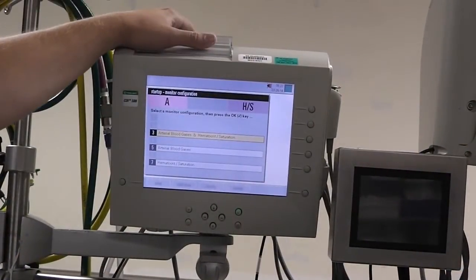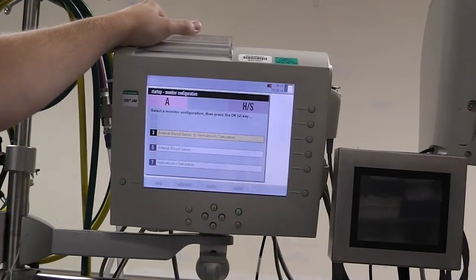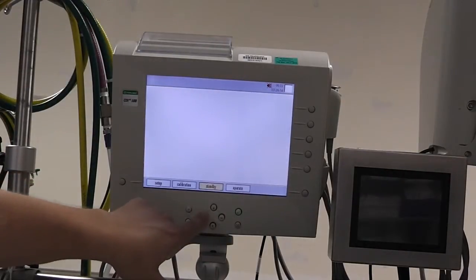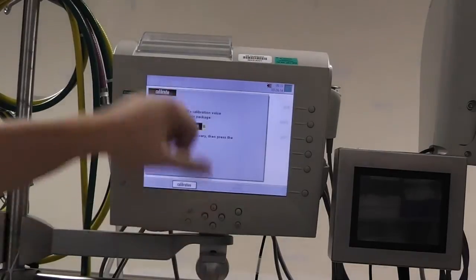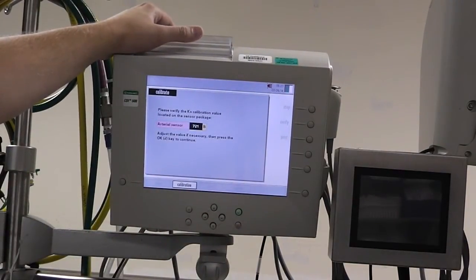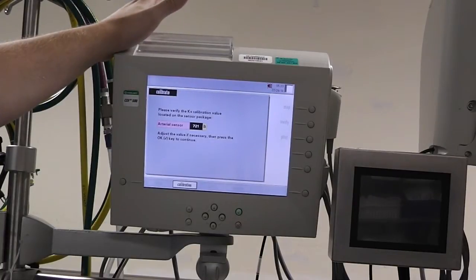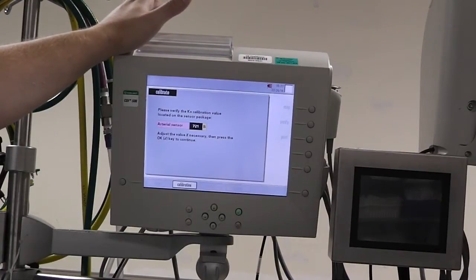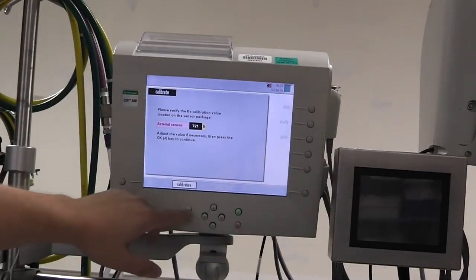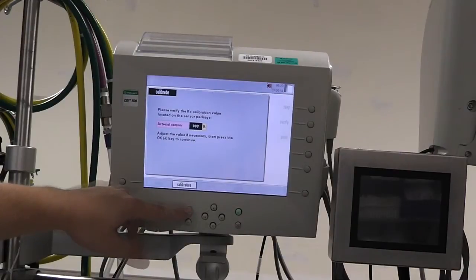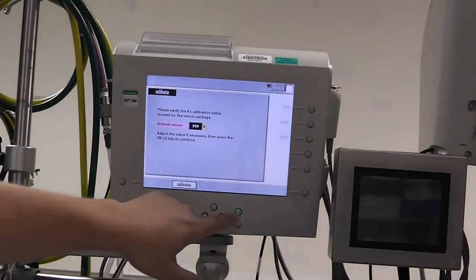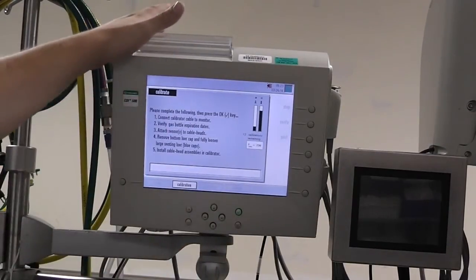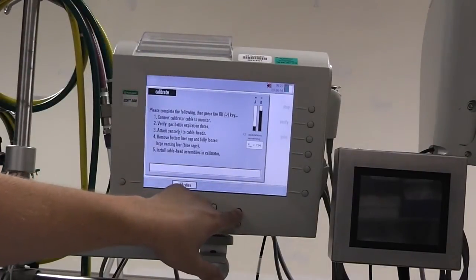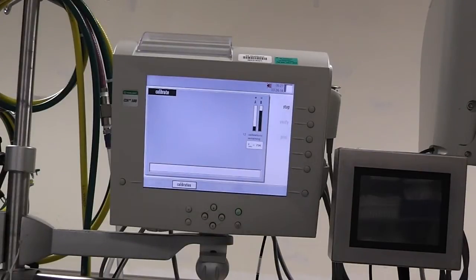So this is the screen that you get on the CDI after it does its initial boot up. It's going to be the first thing that comes up, but it'll say arterial blood gases and hematocrit. You're going to hit the green check to open that. Arrow left to go to calibration, and push the green arrow again. And now here is where we're going to pick the sensor. These things are set up from the factory so that they will calibrate correctly with the correct number here. Ours was 938B, so we need to push the plus button on the left here until we get to 938. If we needed to change the letter, we would do that as well, but that's correct, and we hit the green button there. Now if we have everything already connected, as we do, then we just hit the green button again. And now this will take about 10 minutes, so you want to do this first.